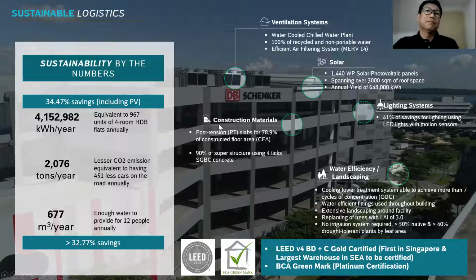In terms of sustainable construction materials, we are using post-tension slabs, as well as Singapore Green Building Council approved concrete structure as part of the sustainability materials we are utilizing. For lighting, we are using LED lights with motion sensors - later I'll show a bit more. For water efficiency and landscaping, we are using cooling tower treatment systems able to achieve more than 7 cycles of concentration, in fact between 7 to 10. Water efficient fittings are used throughout the buildings, with extensive landscaping around the facilities, as well as replanting of trees and flora and fauna with a Leaf Area Index (LAI) of 3.